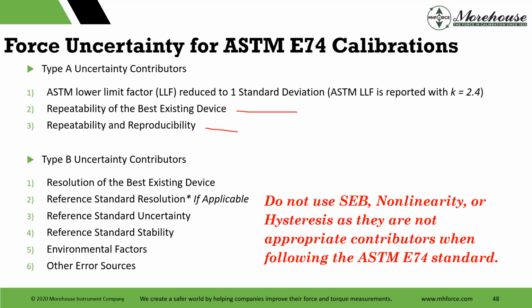Our sheet has that built in. Then you're going to use type B contributors. Since we use dead weight, you're using a load cell that we calibrated for you, you're going to have to use the resolution of that load cell, the reference standard resolution. Dead weight says if applicable, which is 0 with a dead weight because it's a relatively known weight. And then you're going to do your repeatability study with another load cell. Preferably, you buy a really, really good load cell to do this repeatability study if you're using a PCM or something else, and then you use it as an artifact to do your ILCs, inter-laboratory comparisons, and a lot of other things.